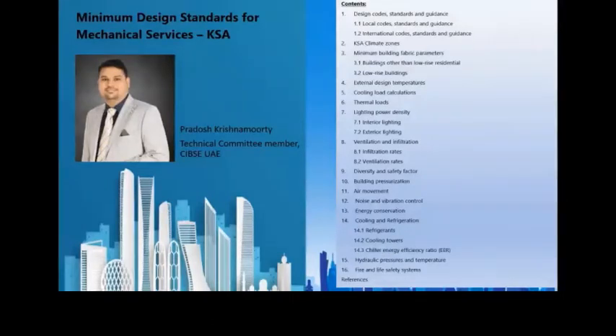And for diversity and safety factor, the SBC codes do not specifically indicate to provide a safety factor, but it is the technical team's recommendation to consider at least 10% for the sensible and 5% for the latent heat loads. And diversity should be judged by the designer specifically. This depends on the project situations, operational scenario of the project, and that should be the basis to decide the diversity of the load factors to be considered. As I said, on the building pressurization system, there are specific requirements to be met, both for the walls, doors, and different elements of the building envelope. So those values should be considered and should be factored in the project design specifications.